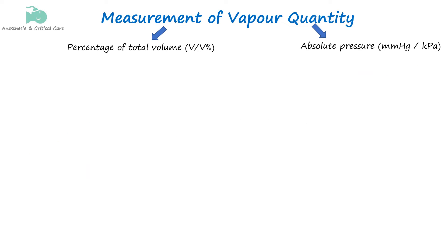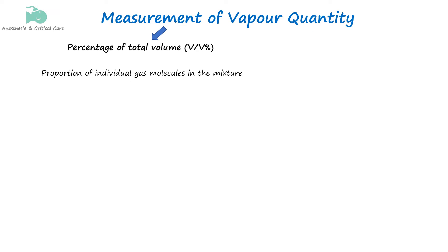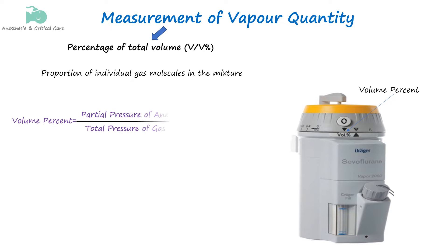Volume percent expresses the relative ratio or proportion of gas molecules in a mixture. The volume percent is a relative measure and doesn't change with pressure or temperature under normal conditions. For instance, if a gas mixture contains 2% sevoflurane, this means that 2% of the gas molecules in the mixture are sevoflurane molecules. The concentration can be determined by the setting on the vaporizer dial and also from the partial pressure measured using a gas analyzer.